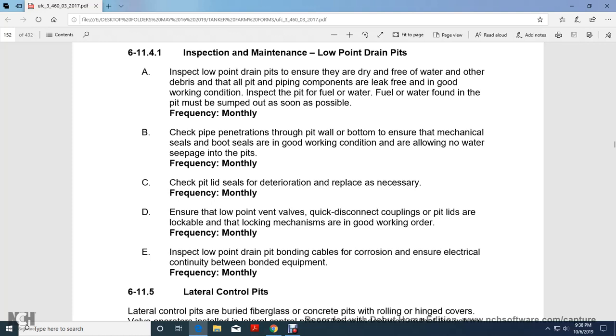Inspect the pit for fuel and water. Fuel and water found in the pit must be sumped out as soon as possible, monthly. Check the pipe penetrations through the pit wall at the bottom to ensure the mechanical boot seals are in good working condition and allowing no water seepage into the pit.